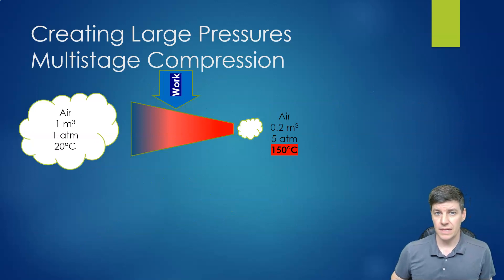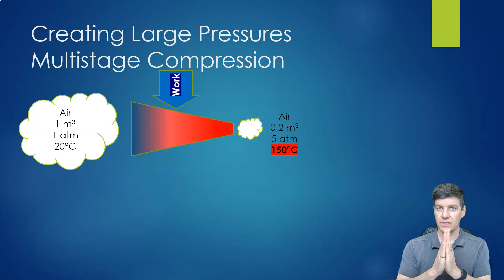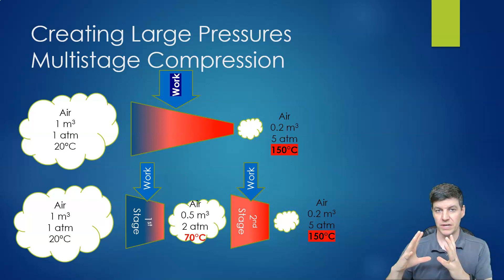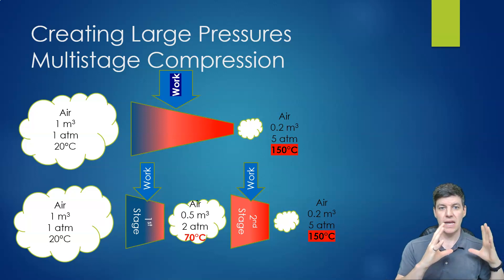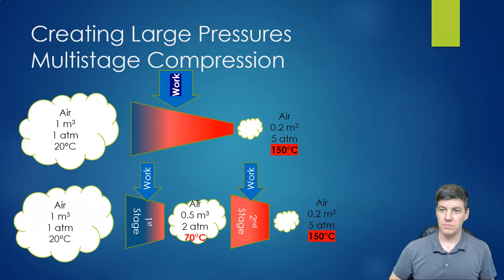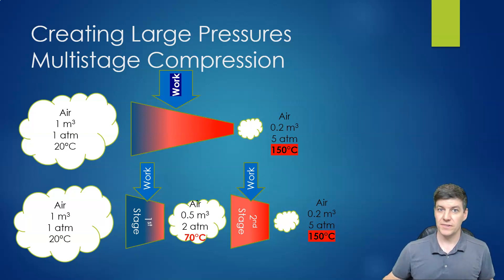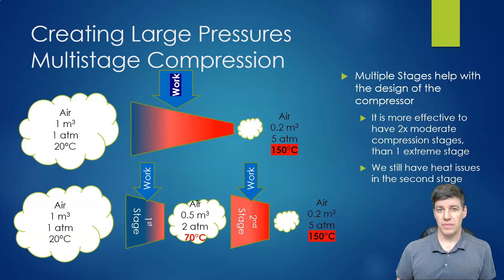So we can break up our compression: instead of one compression stage going the entire way from full volume to minimum volume, we break it up into two separate compressions. We do a moderate compression on the first stage, pass it to the next section, and then do another compression. We could have multiple stages to develop high air pressures. But we run into a problem — our temperature continues to increase through the second, third, and fourth stages. We've solved the physical size issue, but still have an issue with temperature.